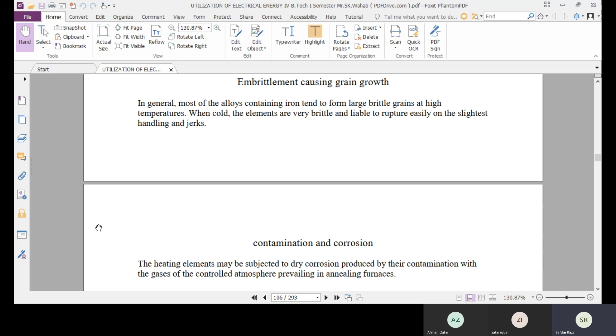So the formation of the grains on the heating element also distorts or destroys the heating element. The last reason is contamination and corrosion. The heating element may be subjected to dry corrosion produced by its contamination with the gases of the controlled atmosphere prevailing in annealing furnaces. The heating element gets corroded whenever it is exposed to the atmosphere, either the atmosphere within the furnace or the outer one. So these are the basic reasons for the distortion of the heating element.